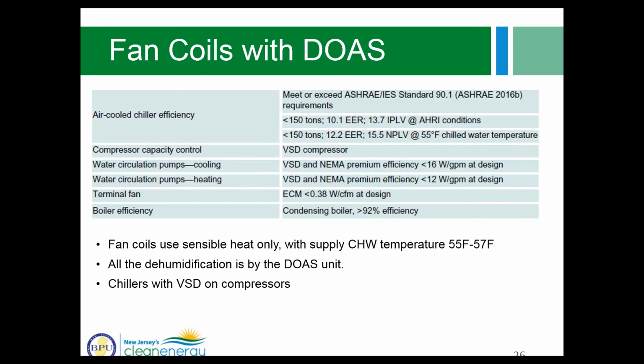These fan coil units, since they do not provide dehumidification, they're located within zones, can have higher chilled water supply temperature, which improves chiller efficiency.